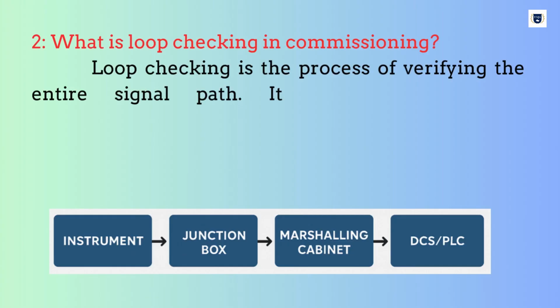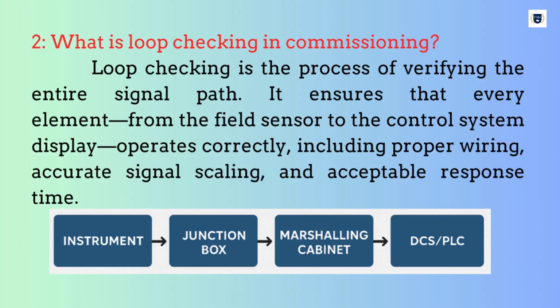What is loop checking in commissioning? Loop checking is the process of verifying the entire signal path. It ensures that every element, from the field sensor to the control system display, operates correctly, including proper wiring, accurate signal scaling, and acceptable response time.